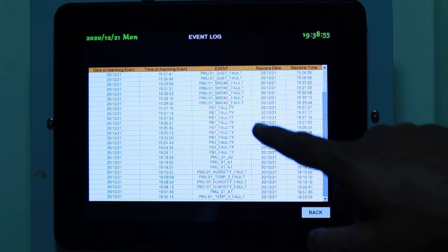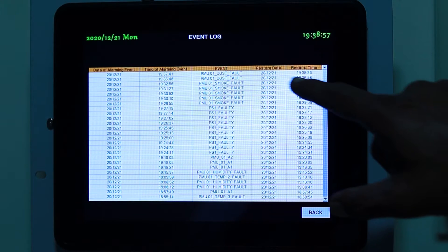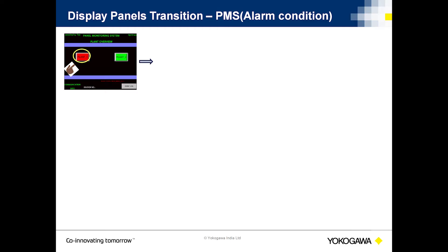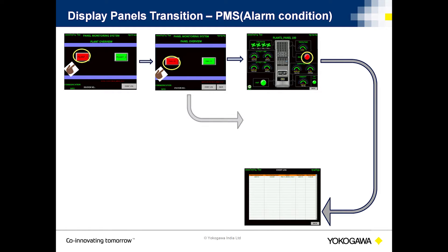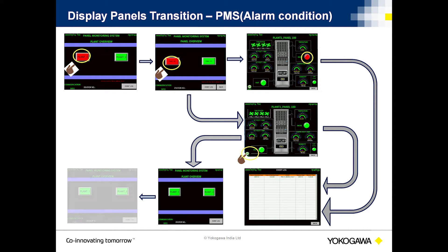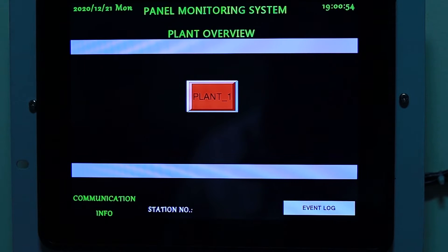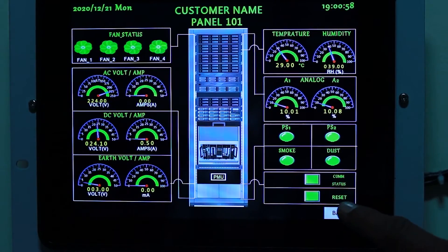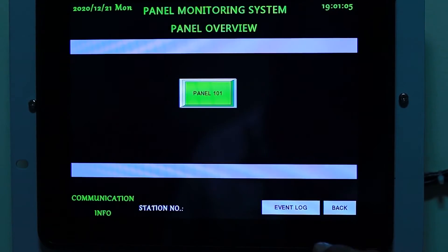To ensure that all alarm events are captured, an alarm log is provided on the HMI which will log all alarm occurrence and recovery events with timestamping. The HMI design features an intuitive hierarchical screen transition system consisting of plant level overview, panel level overview, and finally individual panel parameter display, by which only a glance at the overview can tell if any alarm condition has occurred. Multiple panels of multiple plants can be monitored from a common HMI screen. If any panel of any plant has had an alarm, the plant level box turns red and the corresponding panel level box turns red. The box will remain red until the user notes the alarm and resets it from the specific panel detail display.